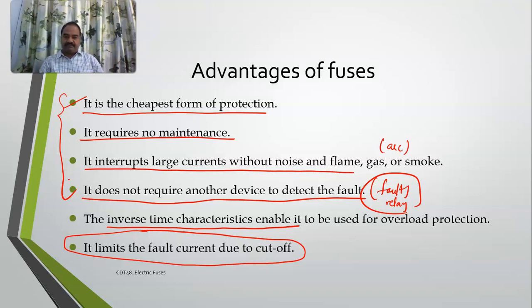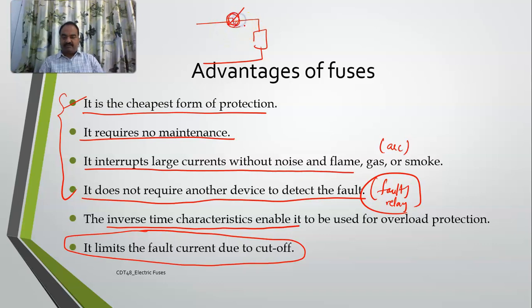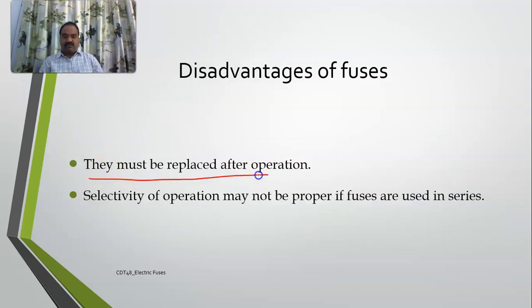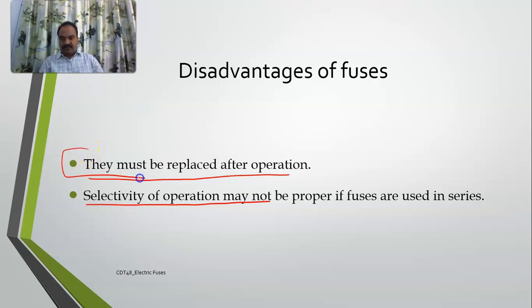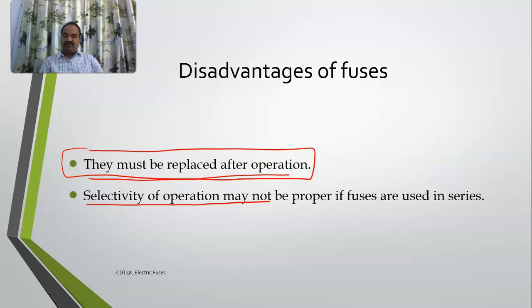The disadvantages of a fuse: when it blows, you must replace it — you need to buy a new one and install it. Fuses must be replaced after every operation. If multiple fuses are used in series, the selectivity of operation may not be proper, which is one of the biggest problems. This is also one of the main reasons why fuses are now being replaced by circuit breakers.